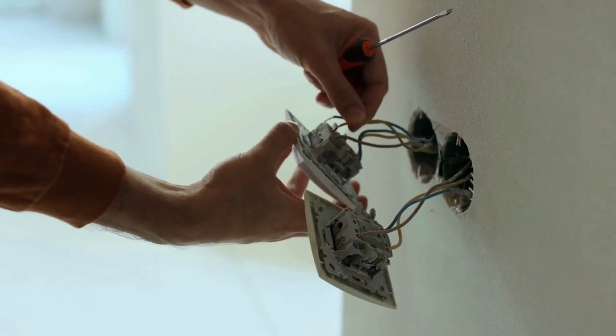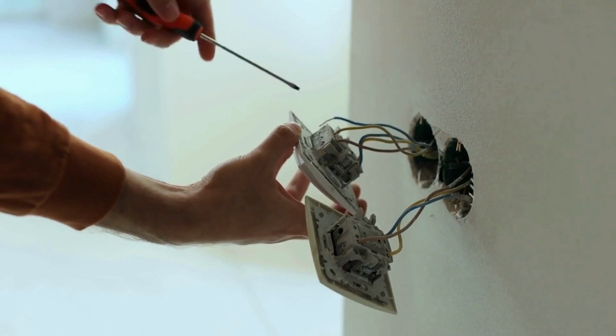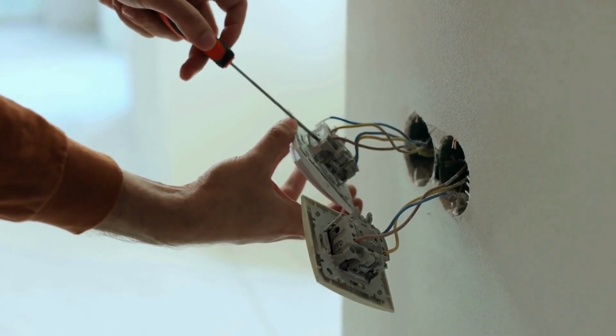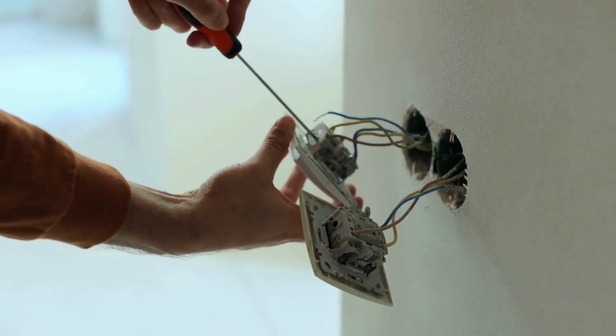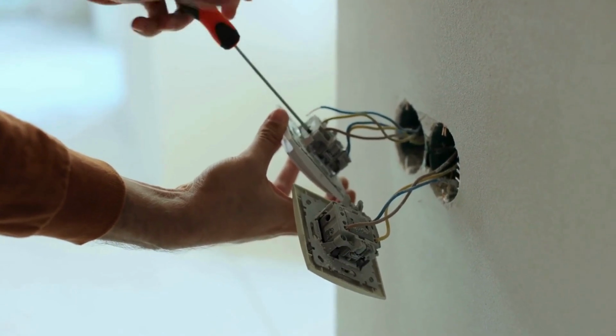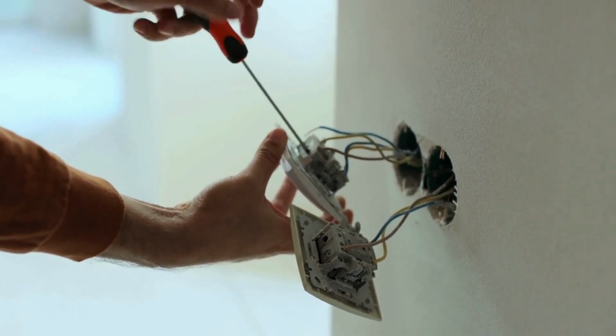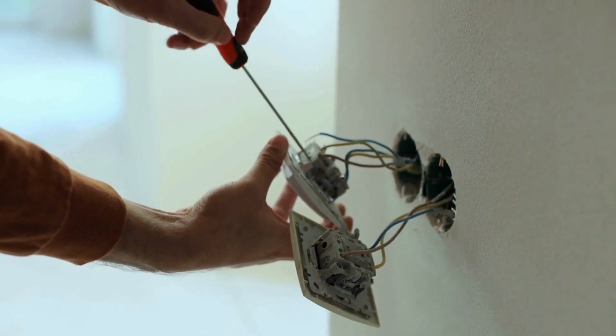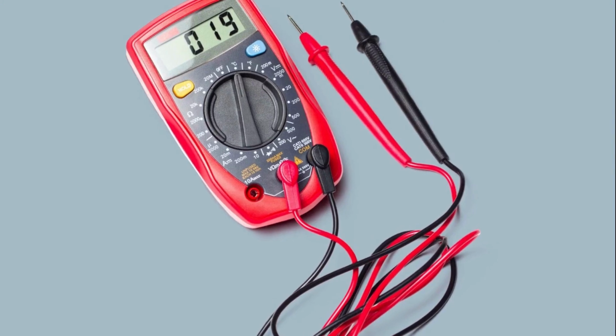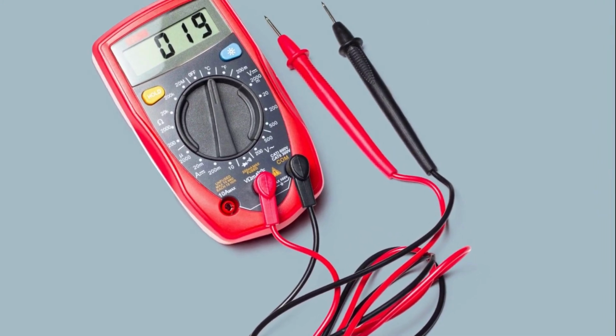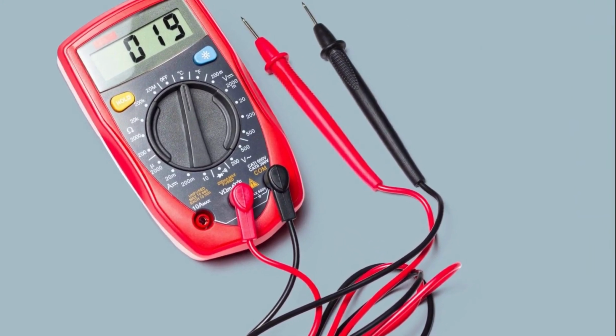If you're working on any equipment with motor drives, power supplies, lighting ballasts, or power factor correction, you need to assume capacitors are present and still charged until you've either verified discharge or waited long enough for them to bleed down naturally. Your voltage tester can't always see stored energy, which means you need to use time and proper procedures as your real protection.